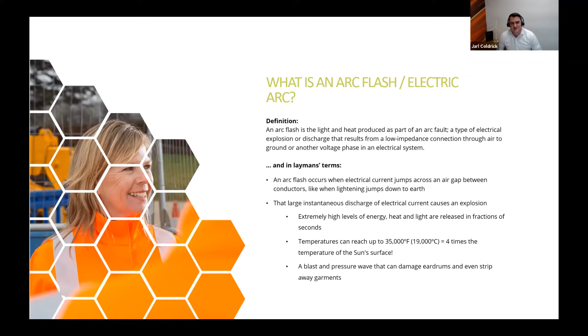That in effect actually causes an arc explosion, and that can be likened to a bomb. It releases extremely high levels of energy. Heat and light are released in fractions of seconds. This happens in milliseconds, but the results can be devastating. It can reach temperatures of 19,000 degrees Celsius, which is 4 times hotter than the surface of the sun. It can also give a serious blast and a high pressure wave that can damage eardrums, damage hearing, and even strip away garments. So it's a very serious risk that we need to protect against.